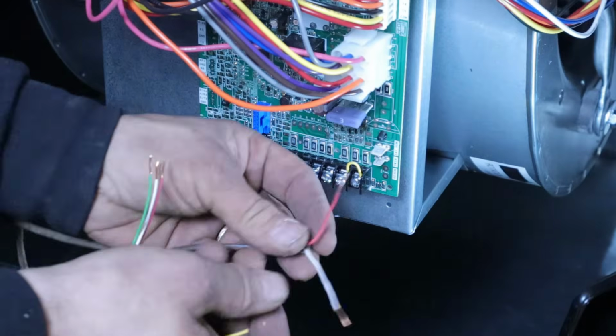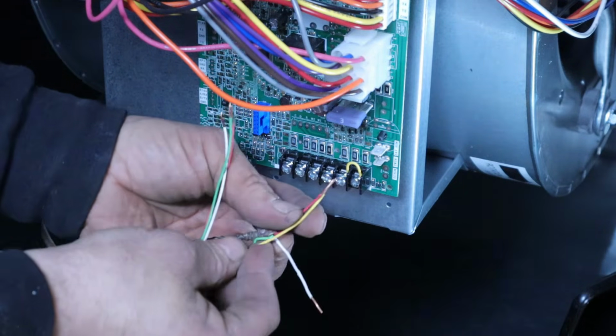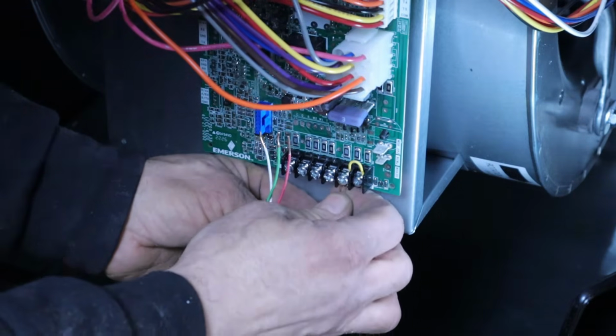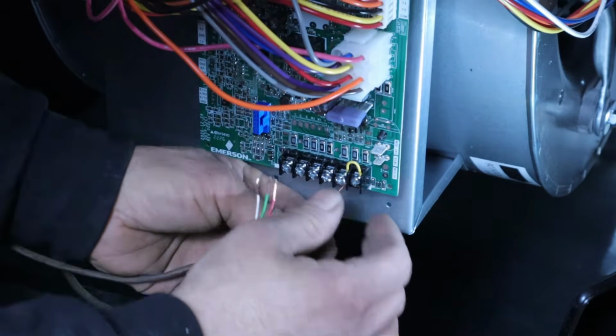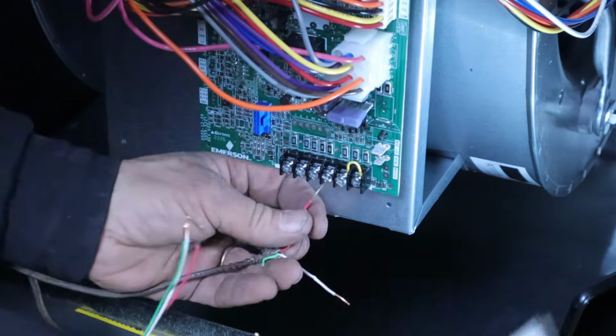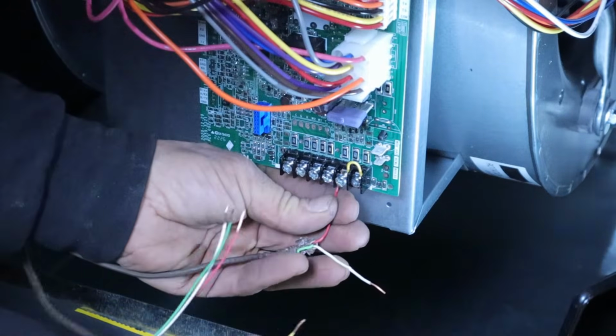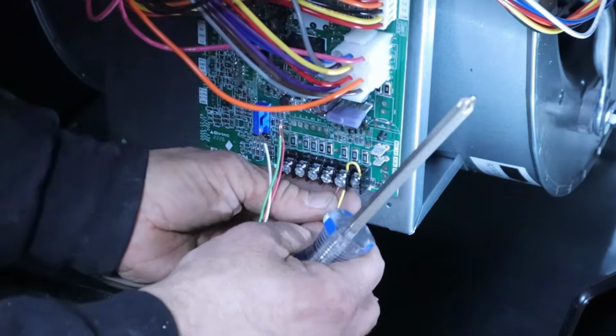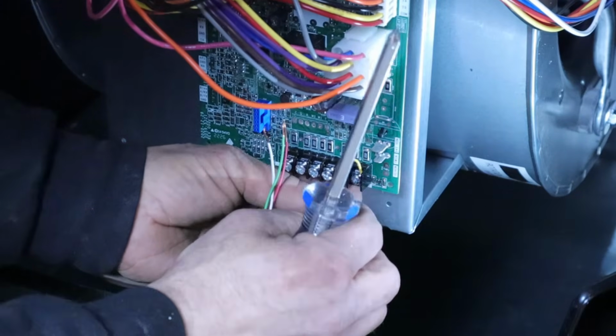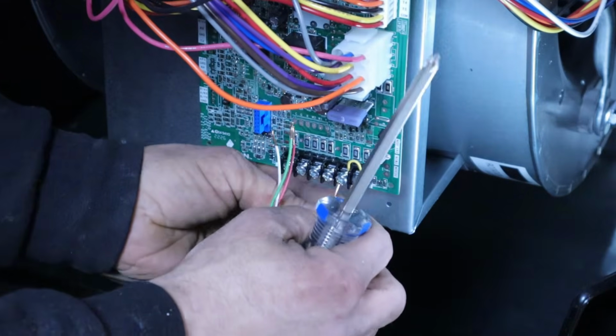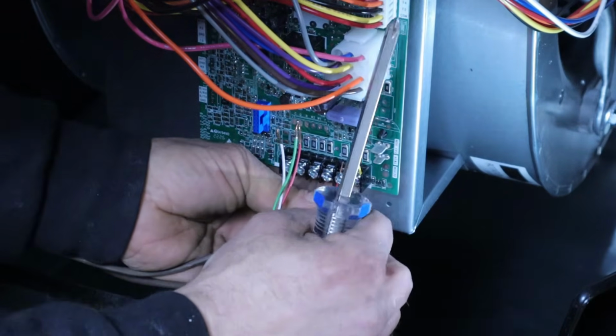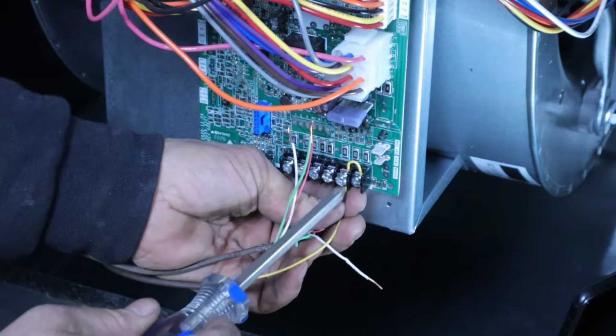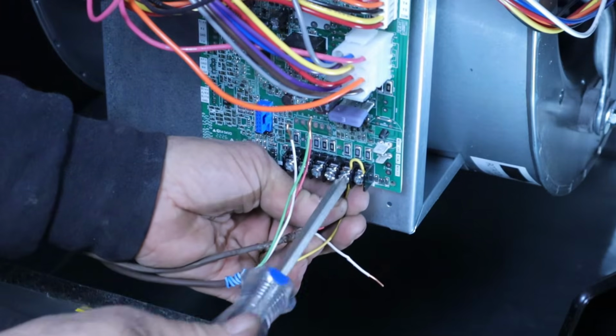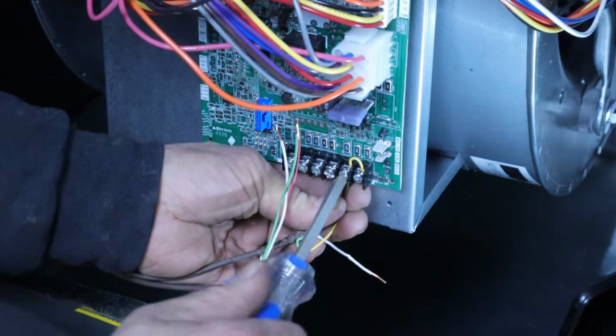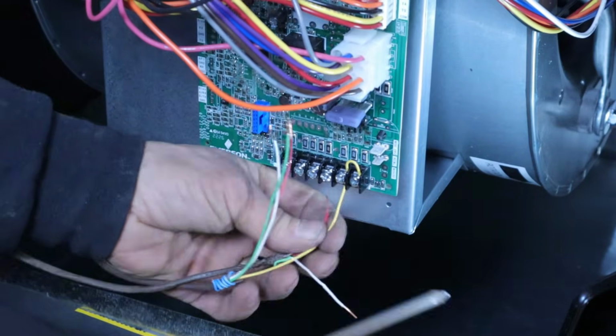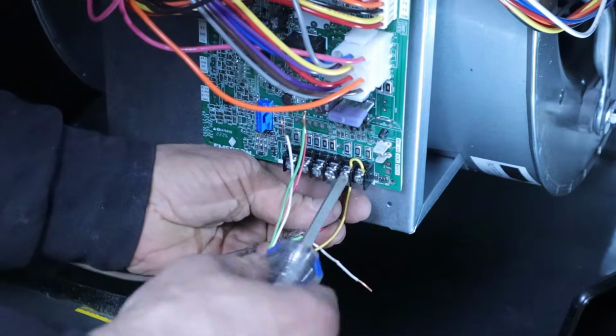So I got my jumper between Y1 and Y2. I'm going to take my red from my condensing unit and the yellow from my thermostat, and tie both of those into Y1. Basically in cooling mode, the thermostat will receive power from the red wire that I'm going to hook up here in a minute. On a call for cooling, it connects the power inside the thermostat from the R terminal to the Y terminal. Then that power comes down along the yellow wire hooked up to the Y terminal, and it's going to power this Y1 terminal.